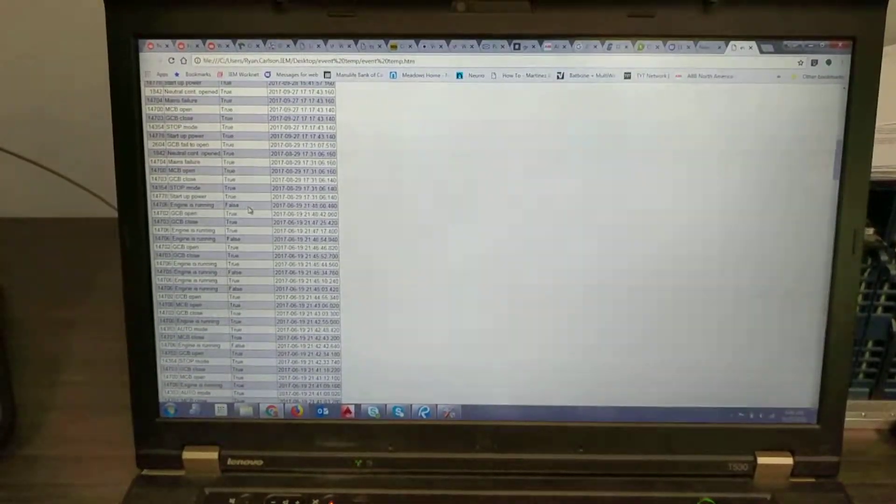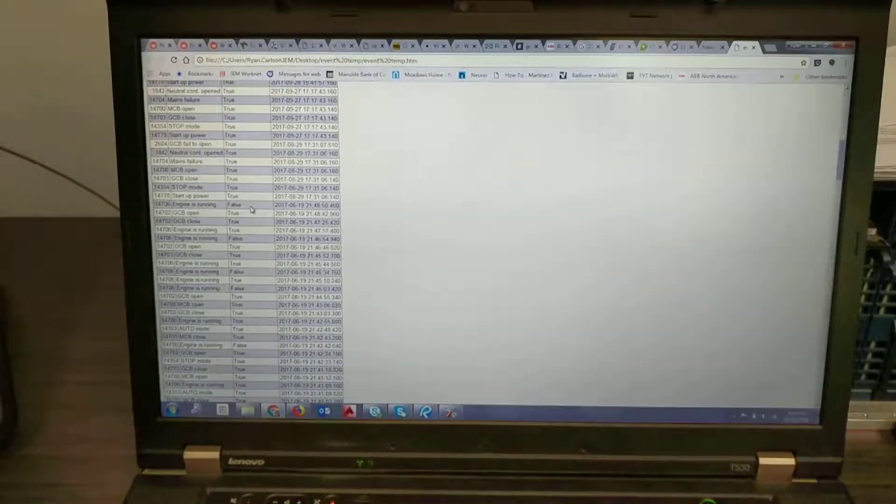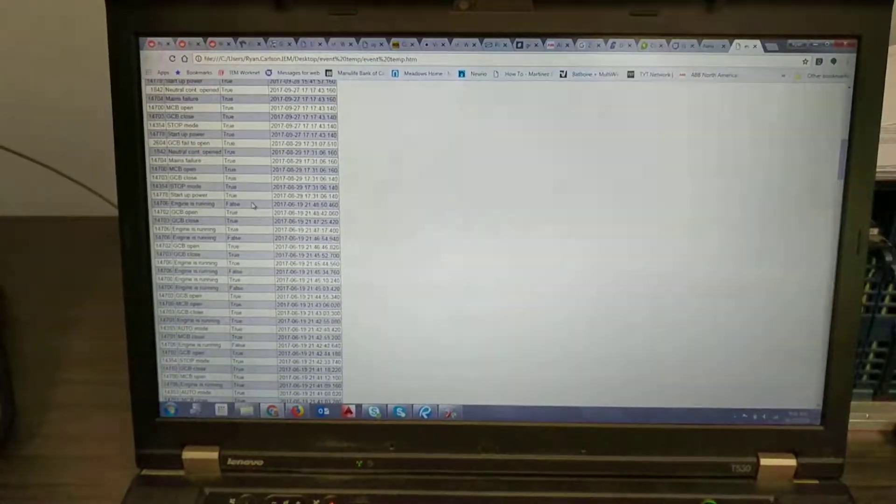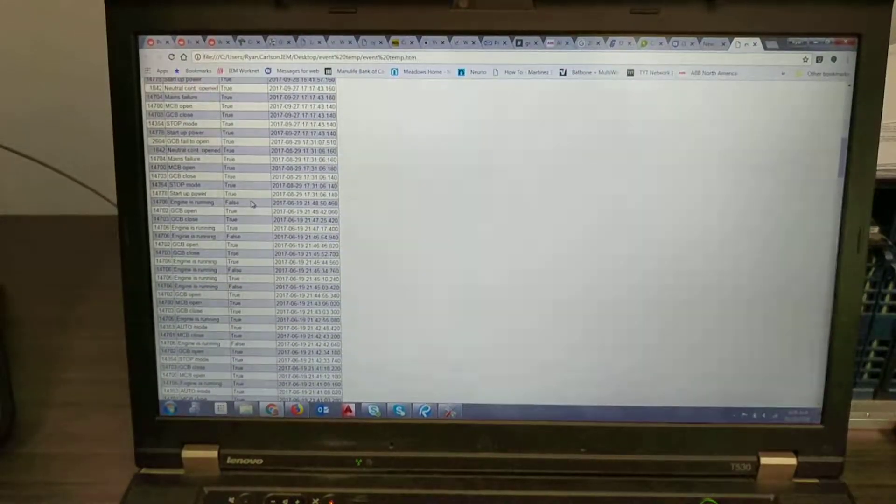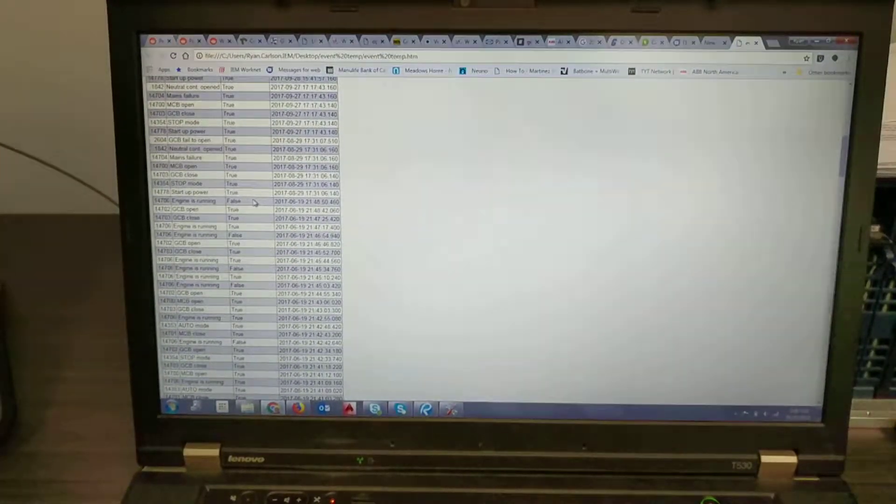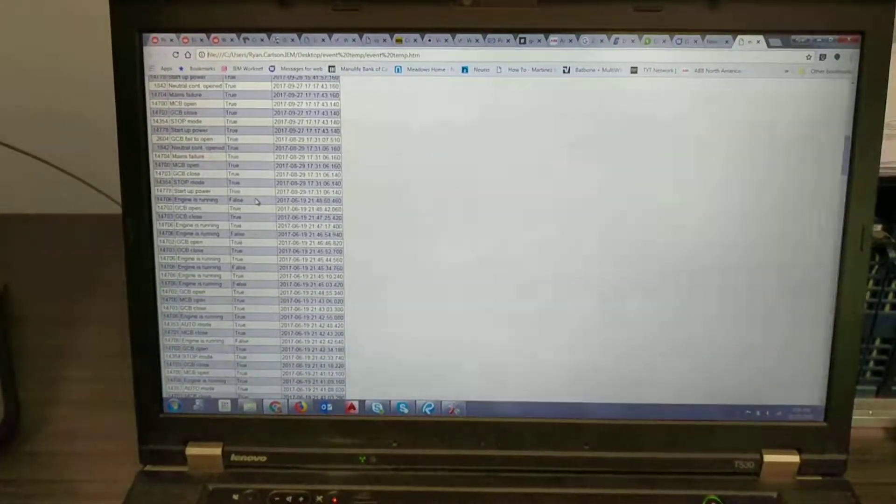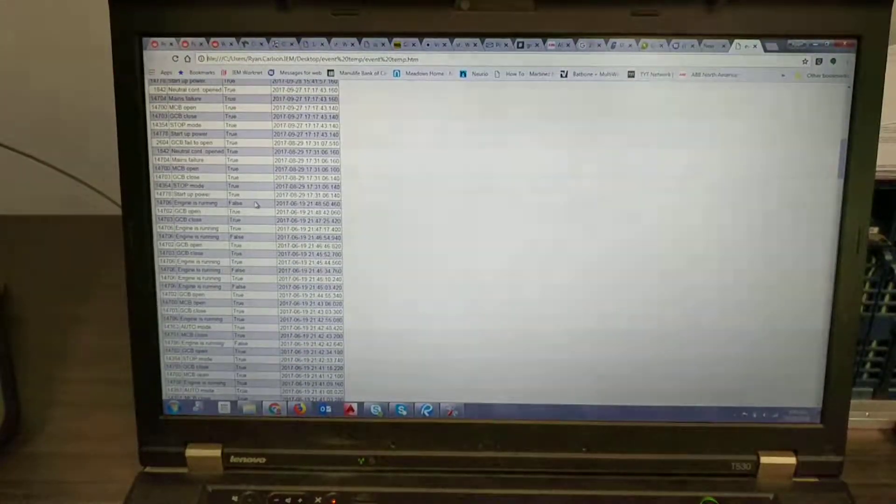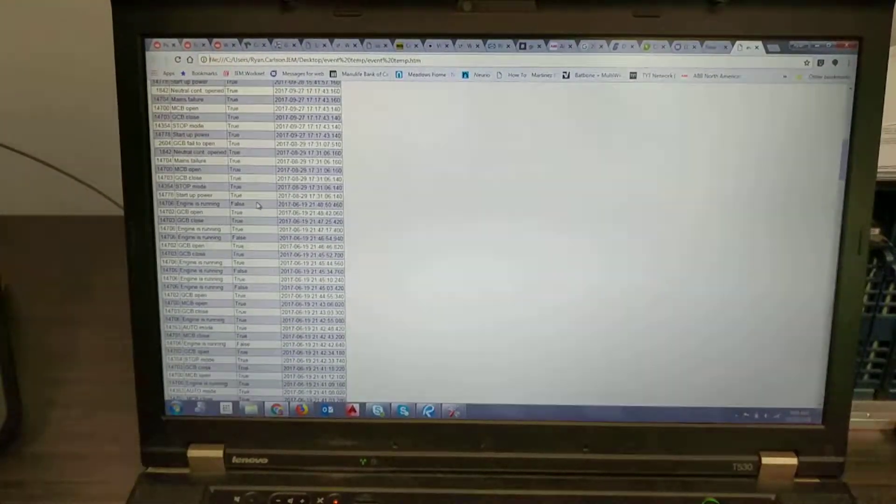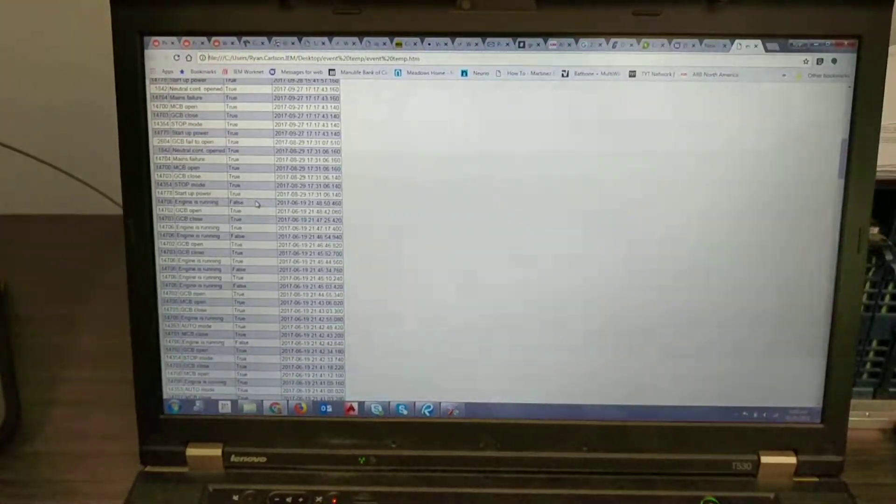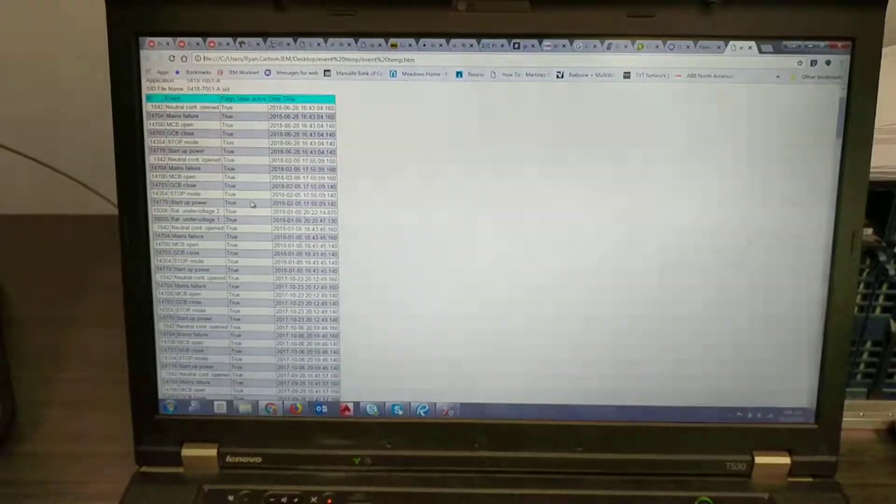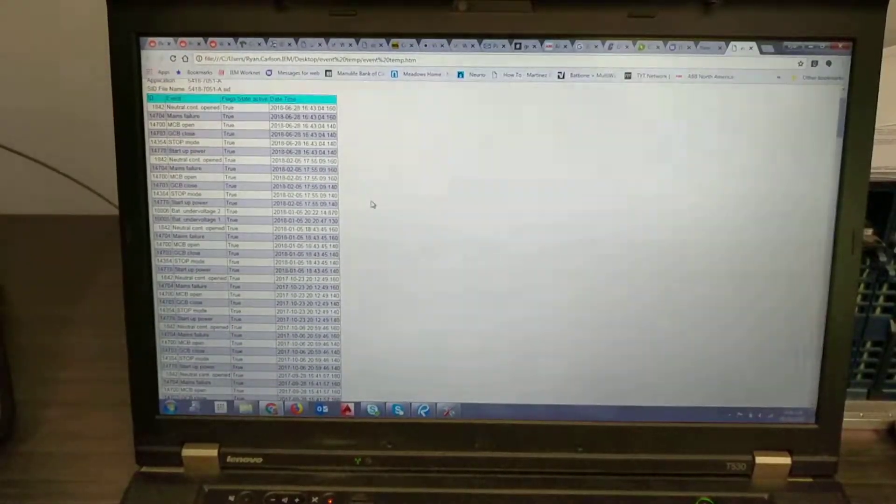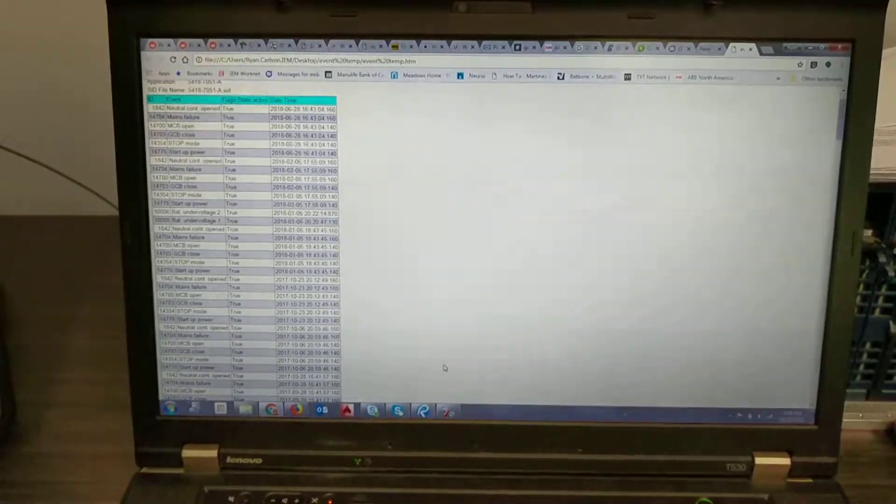So sometimes you'll get one for opening and closing a breaker and then also you'll get one when say a shutdown has been received and then it's been removed or acknowledged. So you can use this to help troubleshoot any issues you're having.